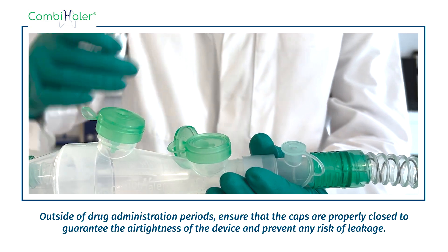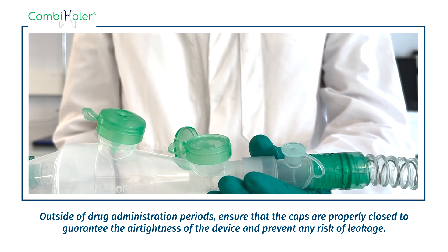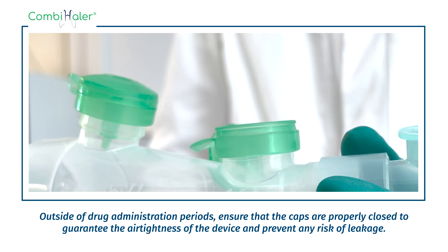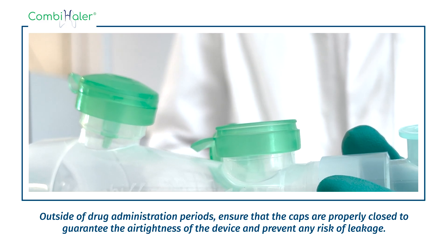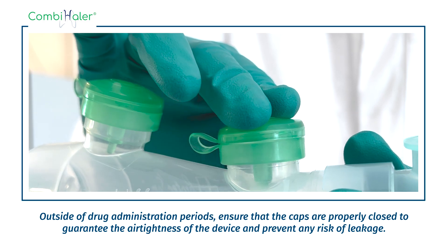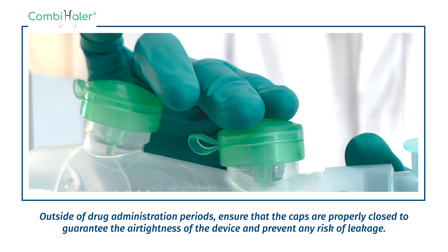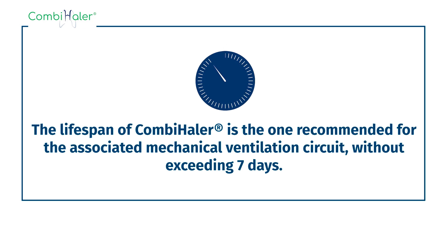Outside of drug administration periods, ensure that the caps are properly closed to guarantee the air-tightness of the device and prevent any risk of leakage. The lifespan of Combihaler is the one recommended for the associated mechanical ventilation circuit without exceeding 7 days.